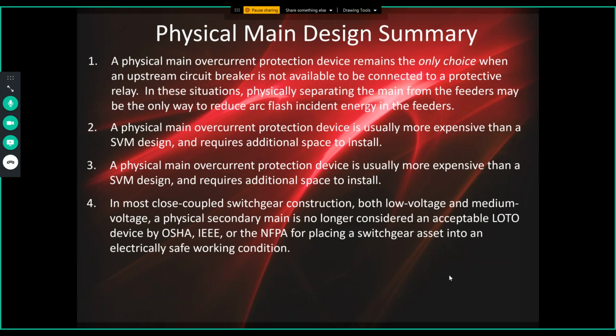In most close coupled switchgear construction, whether you're medium or low voltage, it's no longer even useful as a lockout tagout point per OSHA, IEEE or NFPA requirements. So not only is it useless in terms of arc flash mitigation inside the switchgear if you're close coupled, it's not even a good lockout tagout point.